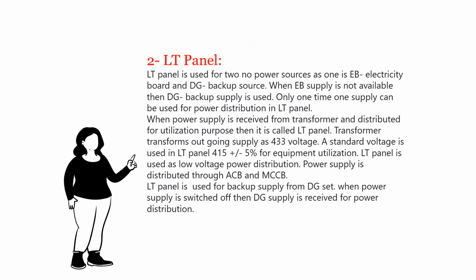LT panel. LT panel is used for two power sources, one is EB electricity board and the other is DG backup source. When EB supply is not available, then DG backup supply is used. Only one supply can be used at a time for power distribution in LT panel. When power supply is received from transformer and distributed for utilization purpose, then it is called LT panel.